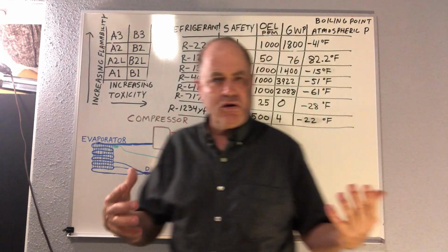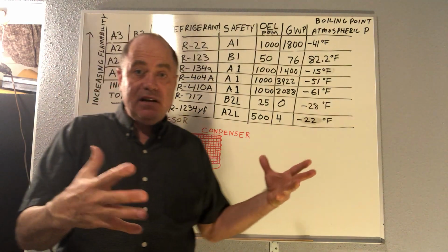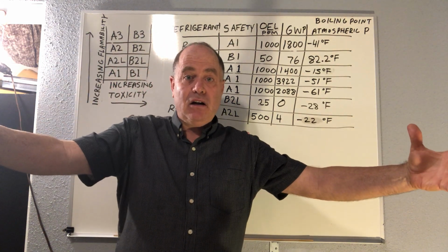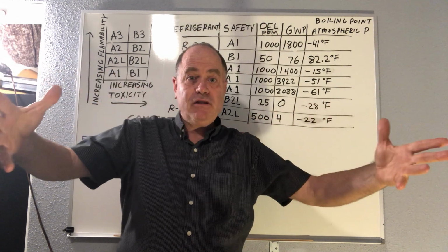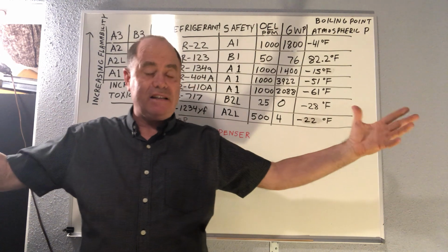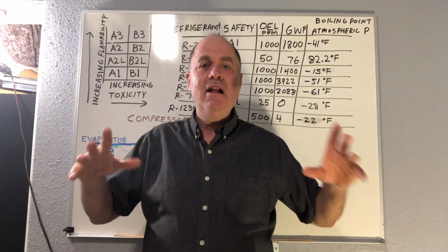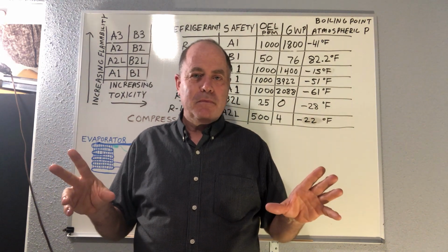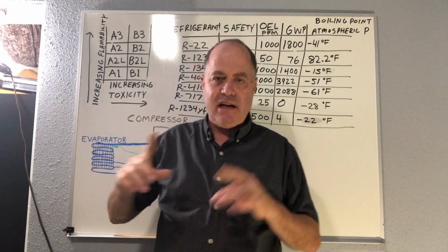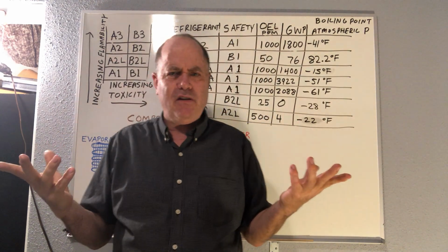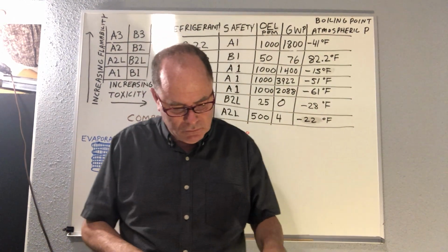So if you had a chiller or something with a lot of refrigerant that in a fire cracked or leaked, now you hit that fire and it shoots out the refrigerant, the refrigerant hits the flame, and now you have a giant ball of toxic gas, and here come the firefighters, a lot of dead firefighters and people in the neighborhood. So before that happens, we'll actually vent all that refrigerant out the roof, outside. So that's the idea. Why we have a pressure relief valve on chillers is for that reason. Okay? All right.